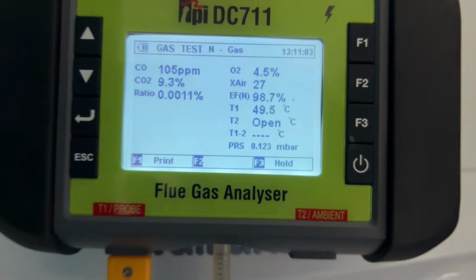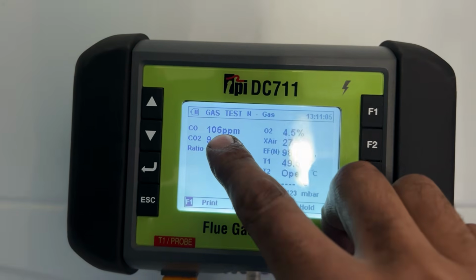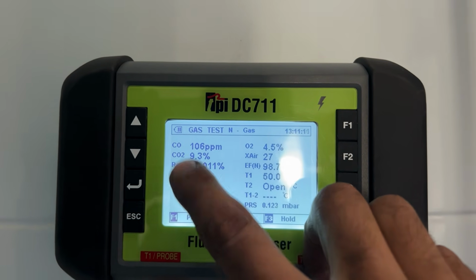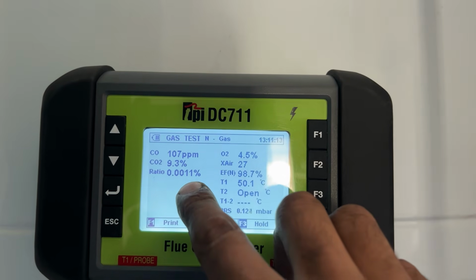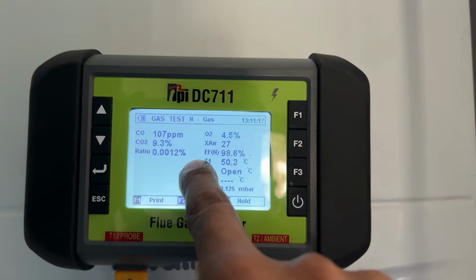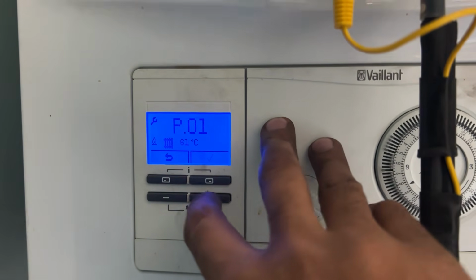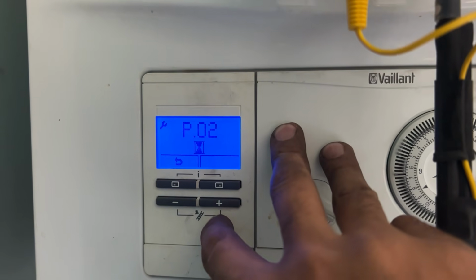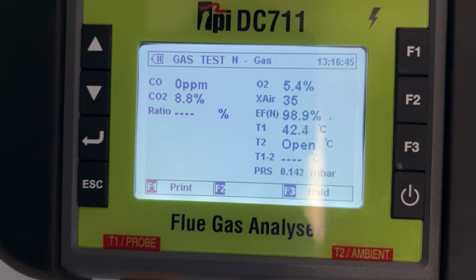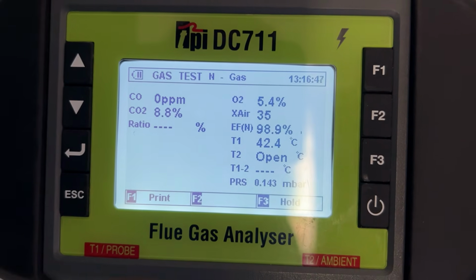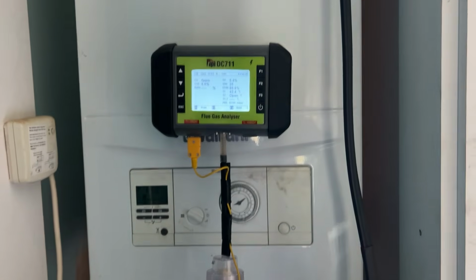So if you have a look at the readings, ppm is under 250. CO2 needs to be 9.1 plus or minus 1, it's bang on. Ratio is bang on as well. Ratio is fine because it's below 0.0035, I believe it says in the Vaillant manual. So maximum's fine. We'll move on to minimum. Make sure minimum is okay. P02. Minimum's fine, 8.8, 0 ppm ratio. Bang on there. Now I'm just going to put it back onto maximum.